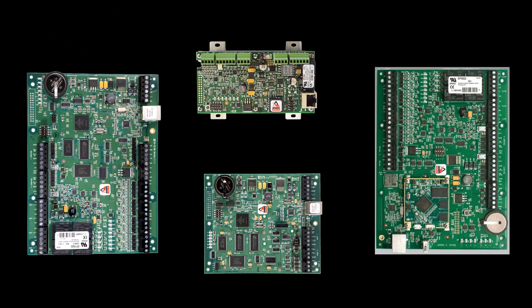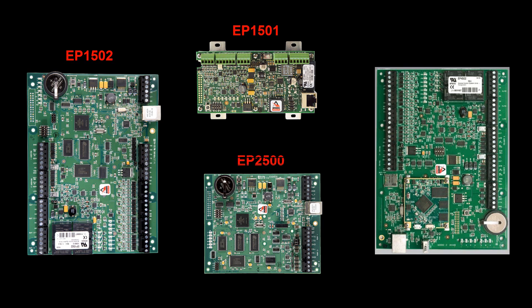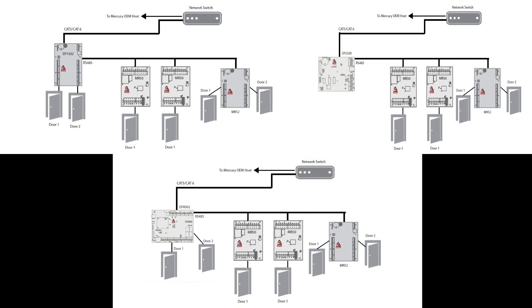The MR50 and MR52 can connect to all Genetec-supported Mercury EP panels, the EP1501, EP1502, EP2500, and EP4502. In these diagrams we demonstrate how the MR panels are daisy-chain connecting to the EP controller using the RS485 bus. You can have a mix of both MR50 and MR52 sub-panels on the same bus channel.